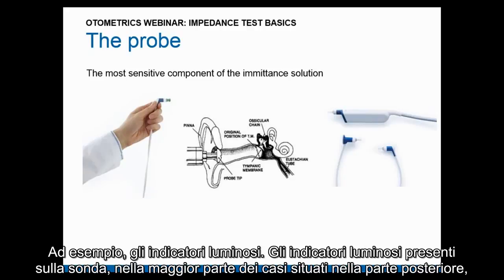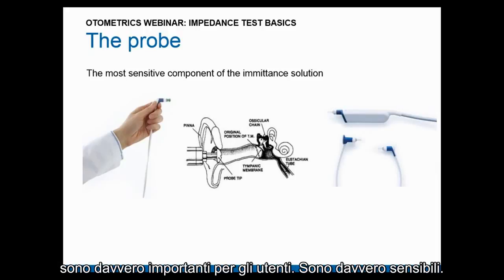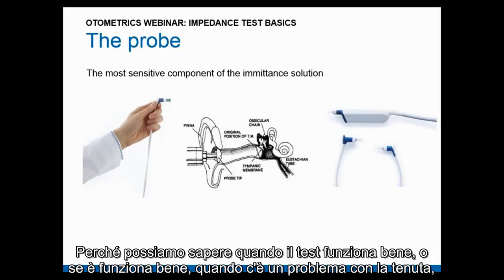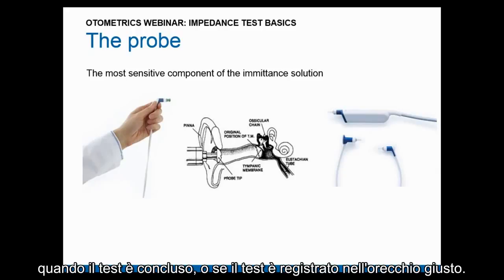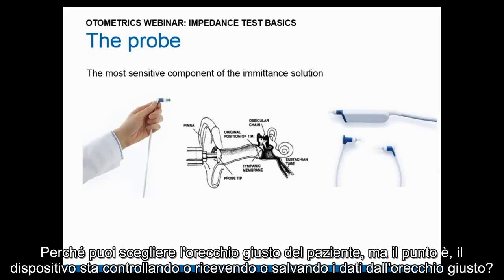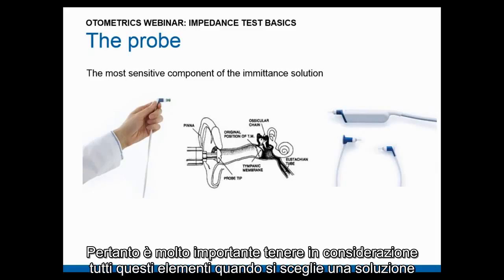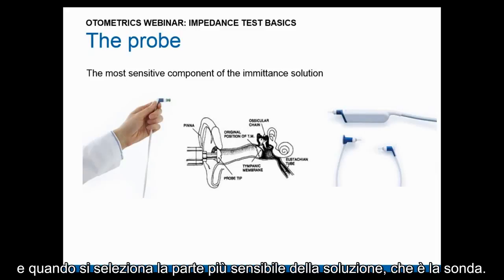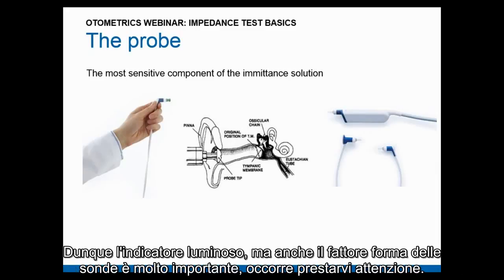The controls I'm talking about include light indicators — found on the probes, most often located at the back of the probe. These are very important for users because they tell you when the test is performing, when there's a sealing issue, when the test is complete, and even whether the test is being recorded for the correct ear. All these elements are very important to consider when selecting the solution and its most sensitive part: the probe.